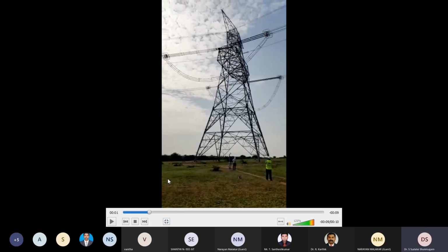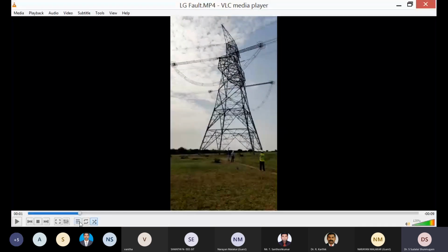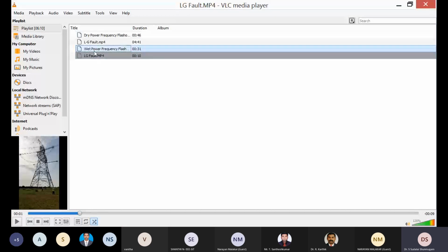Similarly, what you have seen there is a dry power frequency withstand test and flashover test. It means under normal temperature and pressure, without rain, how much voltage it can withstand. But it is not always the case. There will be rainy days also. So under rainy conditions, how much voltage can it withstand? That also we should be aware of.